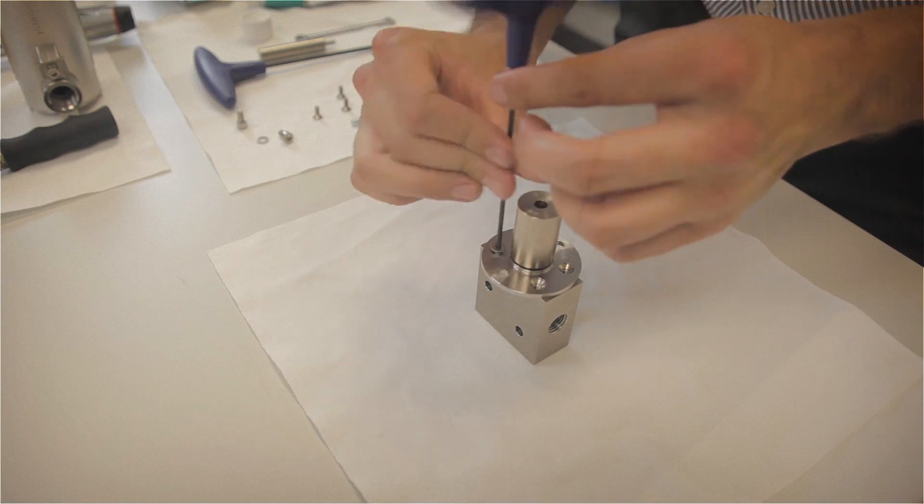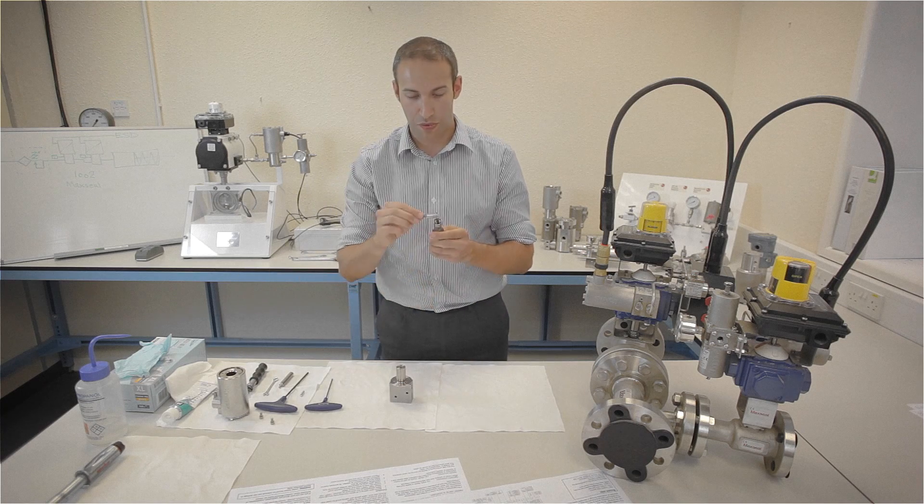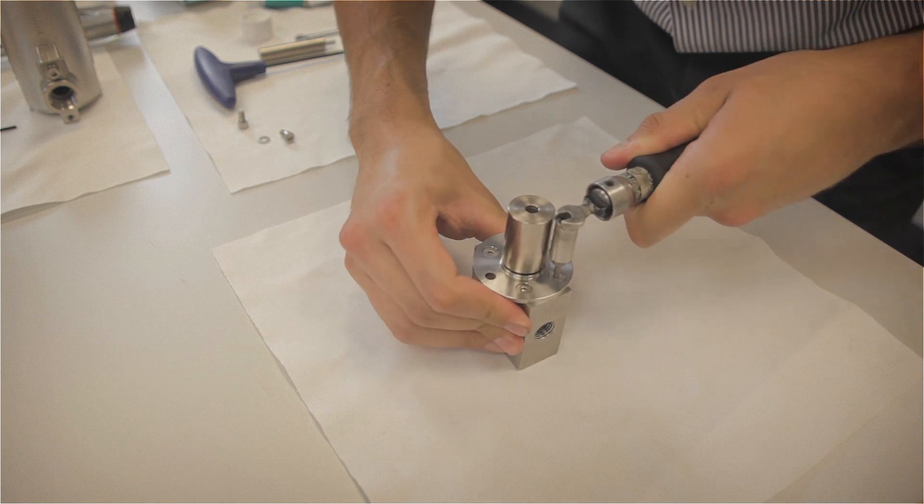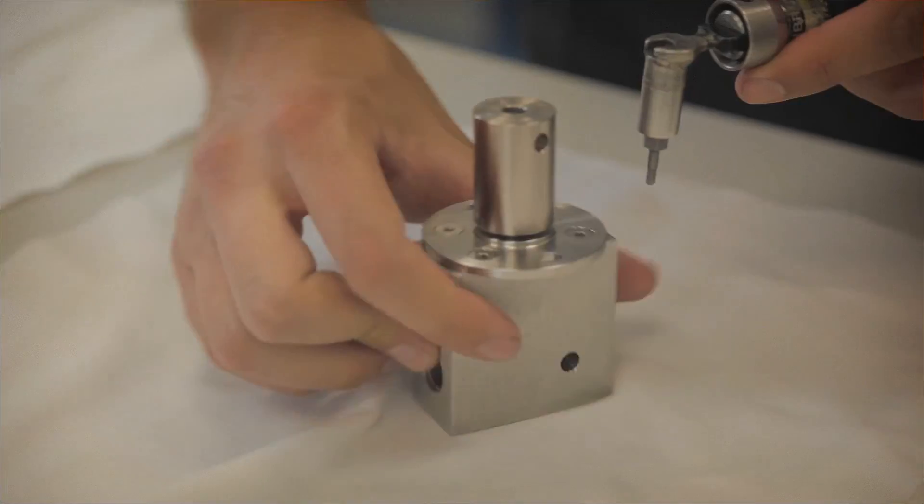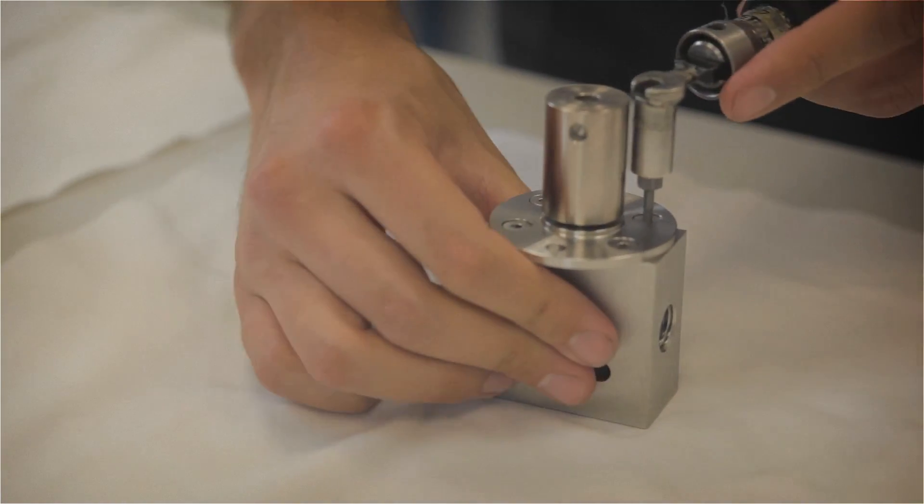You'll then need to take a 2.5mm hex key and screw up the four countersunk screws. Using the torque wrench with the 2.5mm hex key, torque the four bolts in an equal and opposite radial pattern as per the maintenance manual.